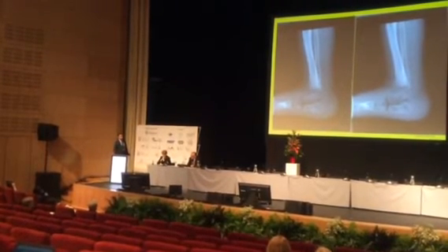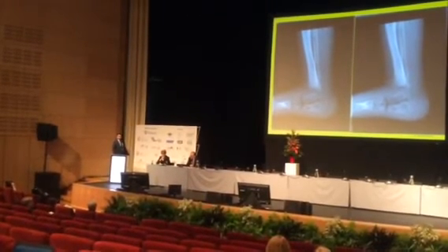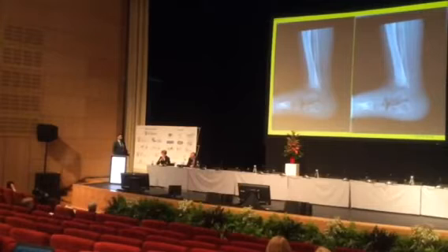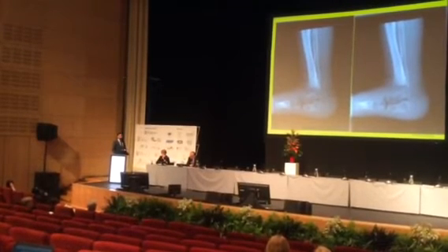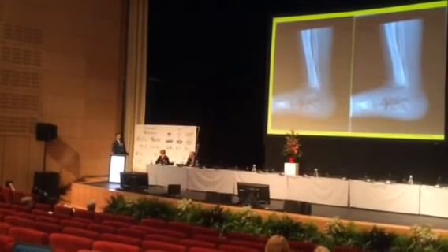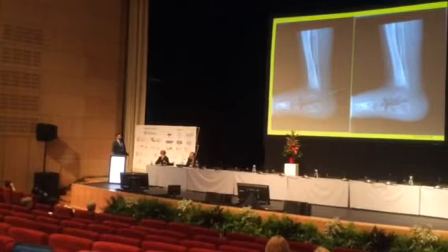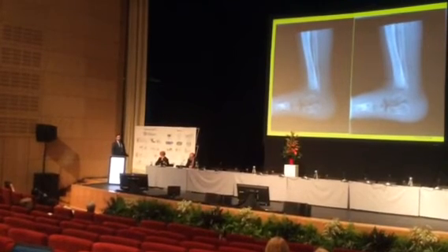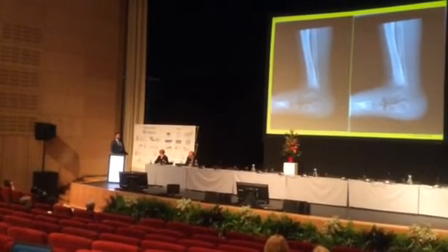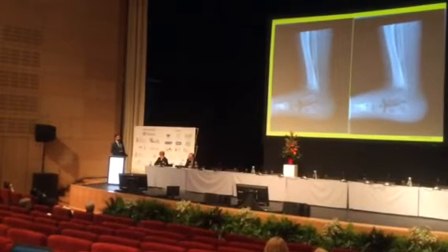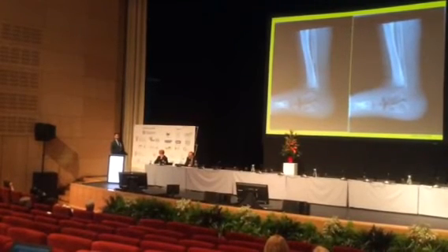And again, although these are only JPEG format, and ideally we'd be looking at these as a DICOM file on a workstation, window level at the same amount. On the left-hand side, we've got the 40 kV and no copper, and on the right-hand side, we've got the default 55 kV with the copper. And again, it's quite clear, even from a JPEG, that there's improved contrast in the image on the left-hand side and less noise.